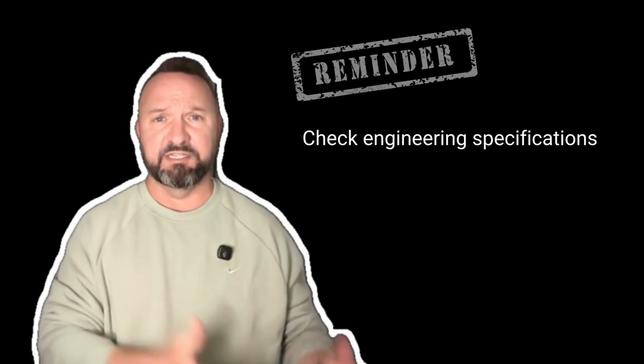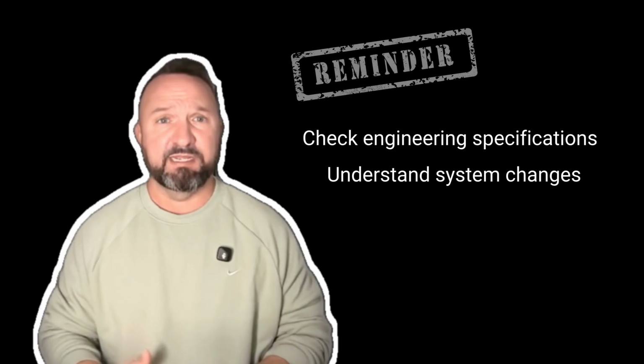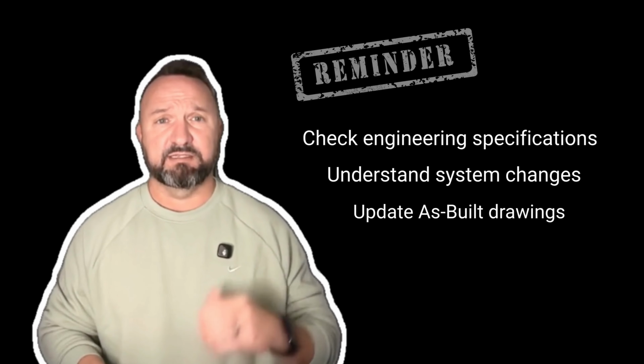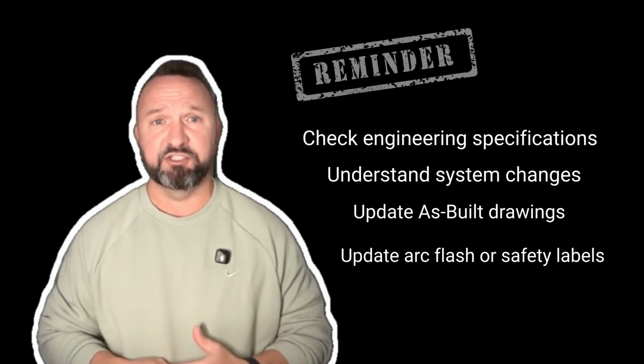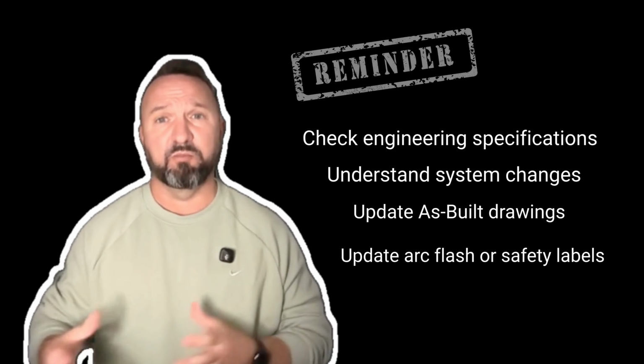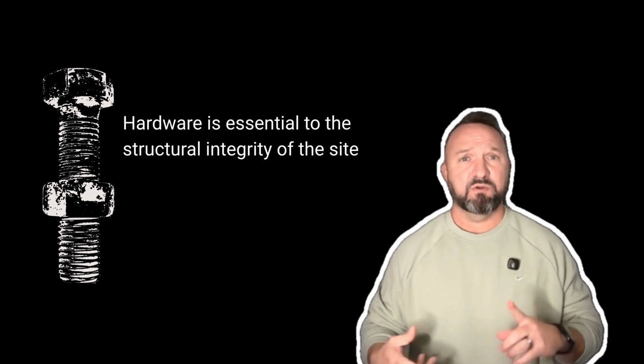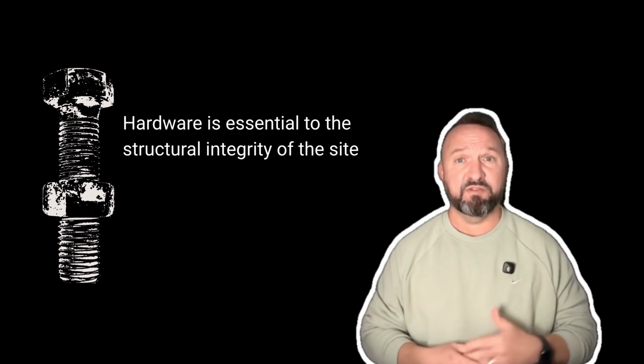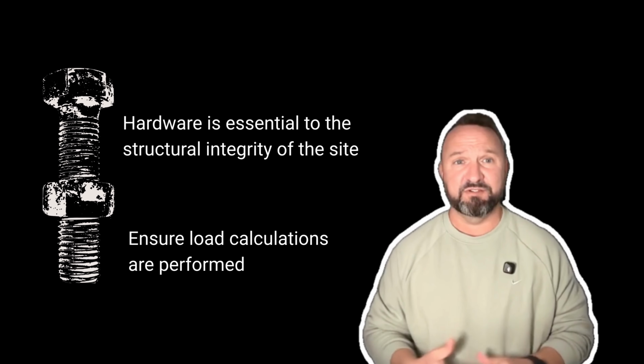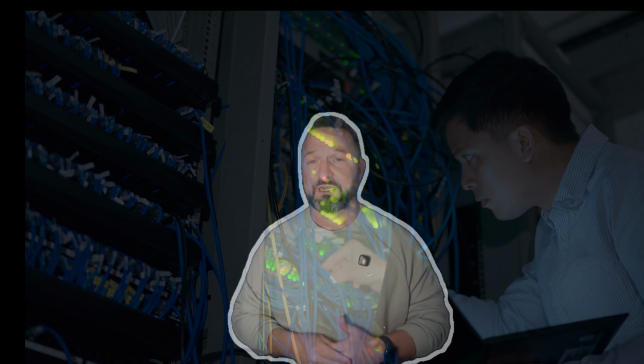Whenever we're changing, whether it's modules or batteries, we've really got to look at the engineering limits when it comes to voltage, the ratings, and the protection settings. Changes could affect the string voltages, the DC to AC ratios, and the inverter maximum power point tracking algorithm and ranges. On the mechanical side, new solar modules or battery modules may be heavier than the original. So engineers might have to look at different tracker structures, mounting systems, or foundations that can support the new equipment. Newer equipment may also have different protection settings, and so protection engineers must evaluate the relay coordination, the grounding systems, and the fault condition behaviors.